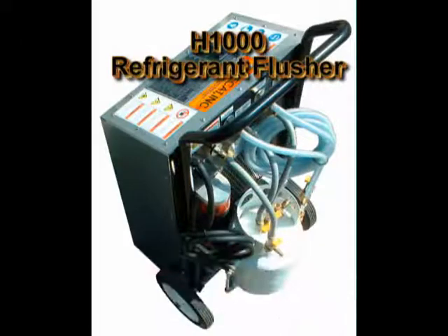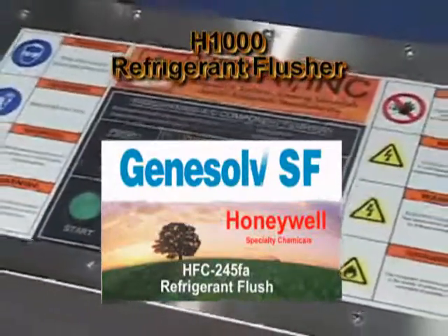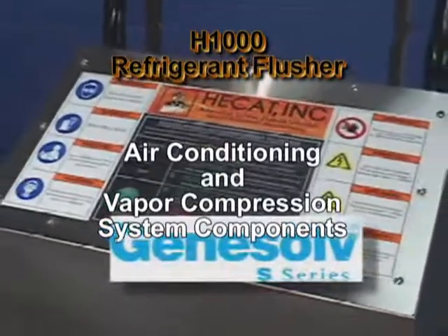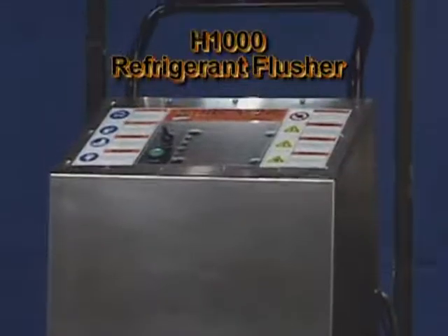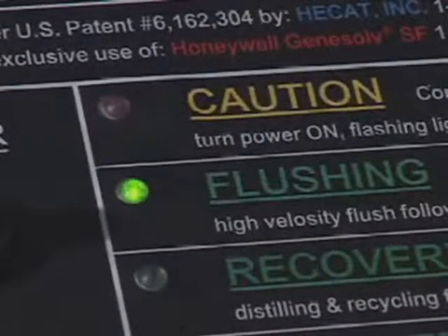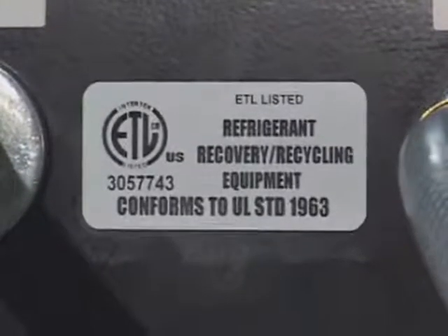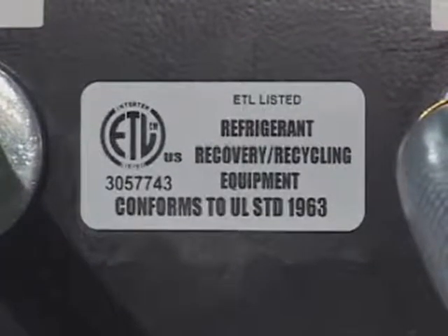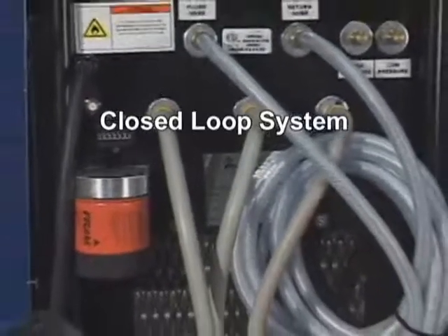The Hecat H1000 combined with Honeywell's Genesolv SF is designed to clean air conditioning and vapor compression system components. The Hecat H1000 is fully automated — just one button and the unit performs the entire flushing process unattended. The Hecat H1000 is ETL certified to the safety standards of UL 1963. This is a closed loop system.